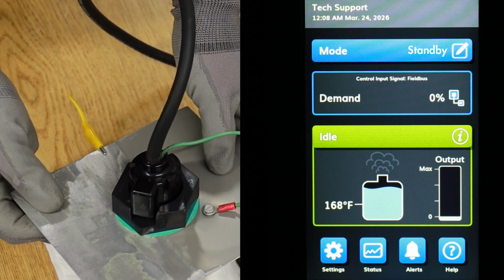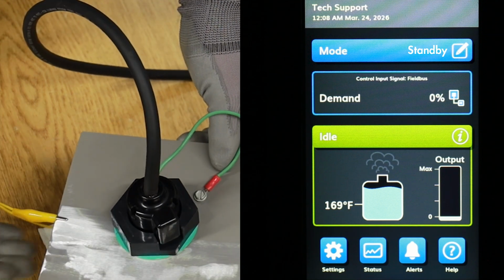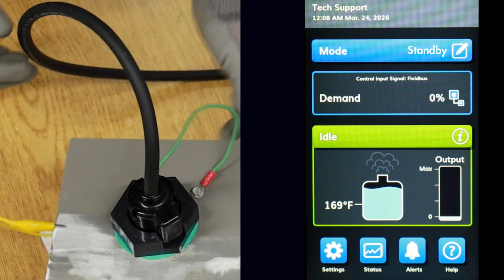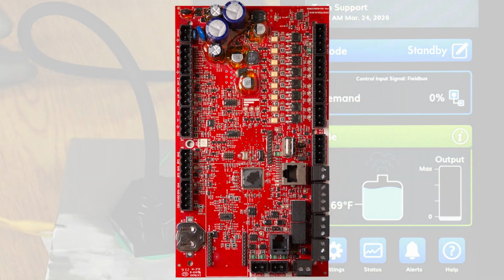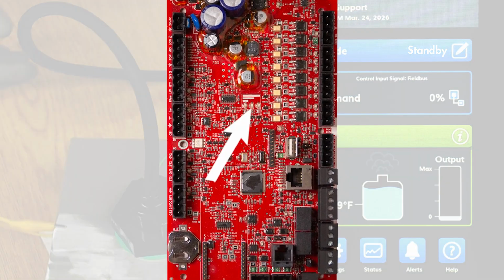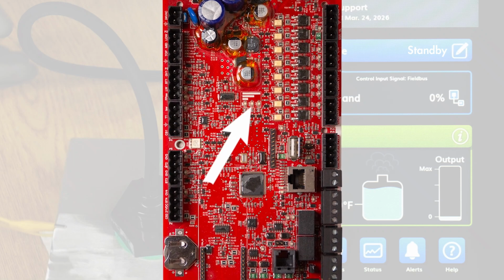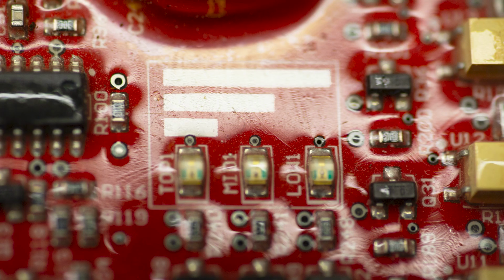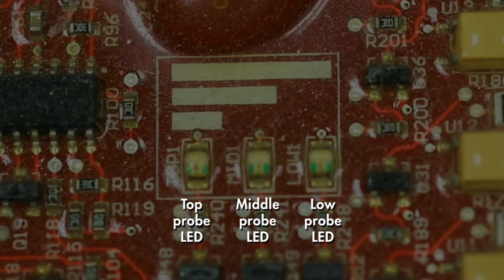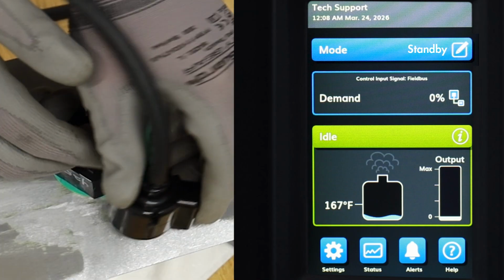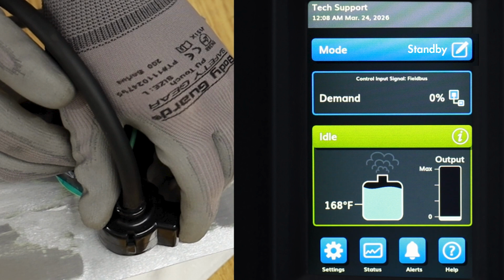The top probe, the shortest, is for sensing foam or high water and does not have a corresponding indicator on the display. You can verify the function of all three probes by watching the probe LEDs on the board. It's a very small area, so we'll get in close. There is an LED for each probe, and they light up in order from low to mid to high as contact is made. You can also test the system circuitry by removing the plug from the probe housing and grounding all three pins to the top of the tank.